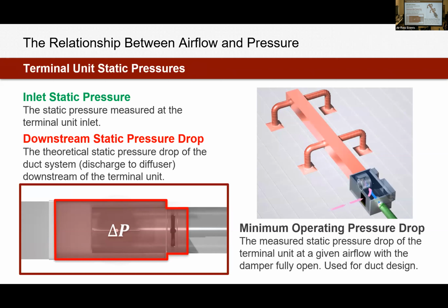We look at a terminal unit installed in a run of duct. For example, we can look at this box over here. The green duct is your inlet duct. This is coming from our air handler. This is where we're going to be measuring and finding our inlet static pressure. That inlet static pressure comes from your air handler. The fan on your air handler is pressurizing all of the duct downstream, and it is providing a positive pressure to the inlet of your terminal unit.